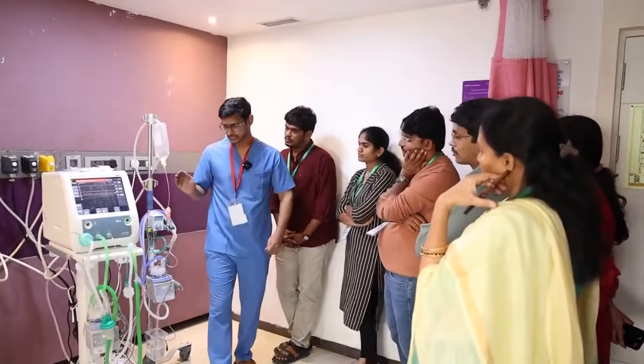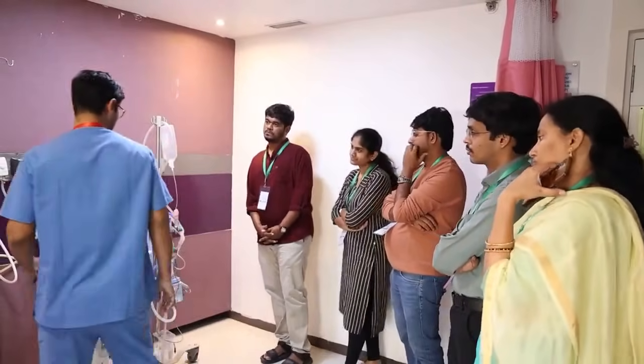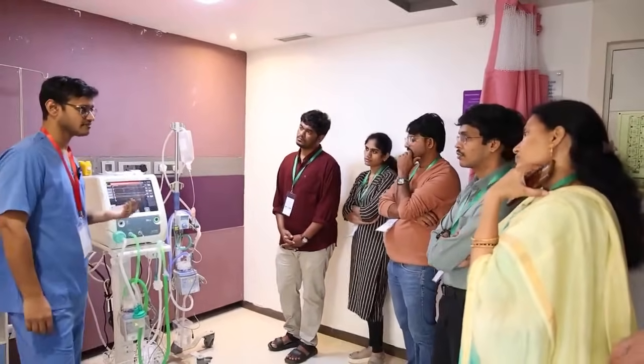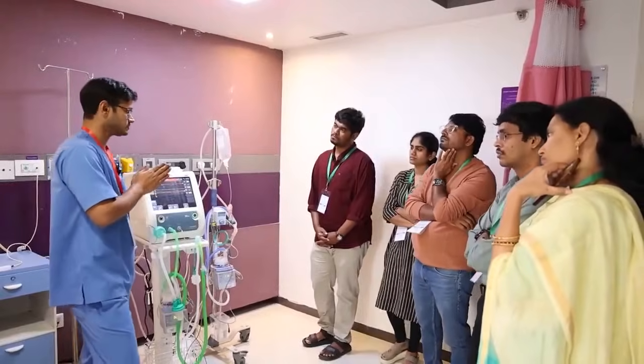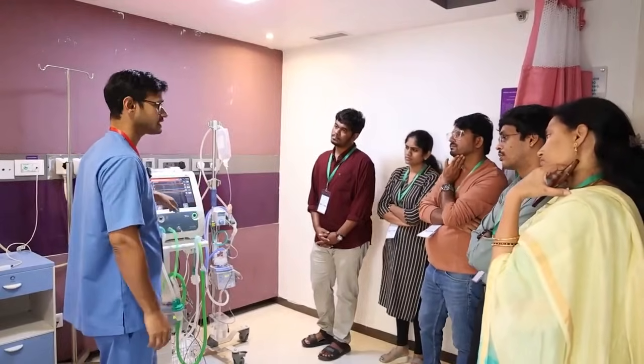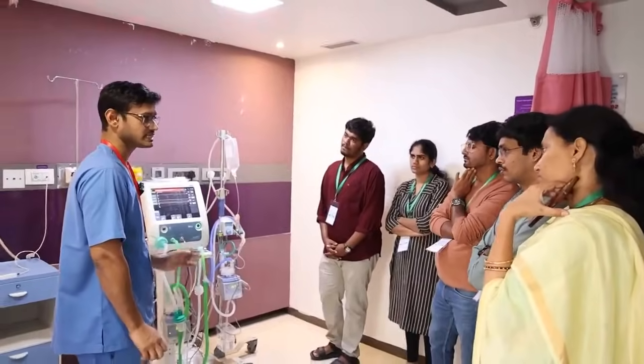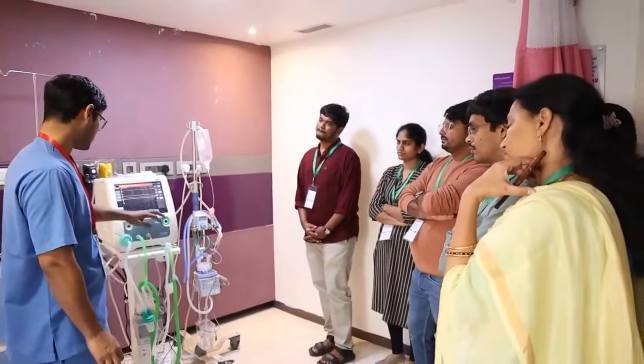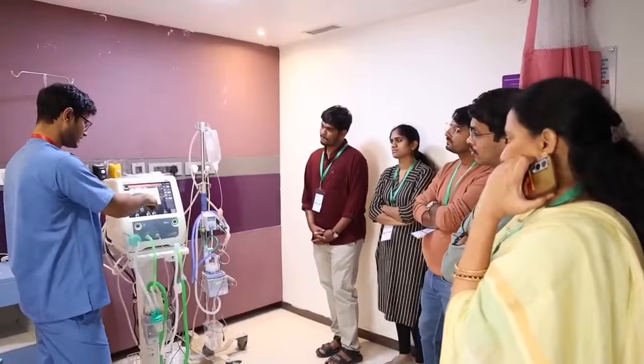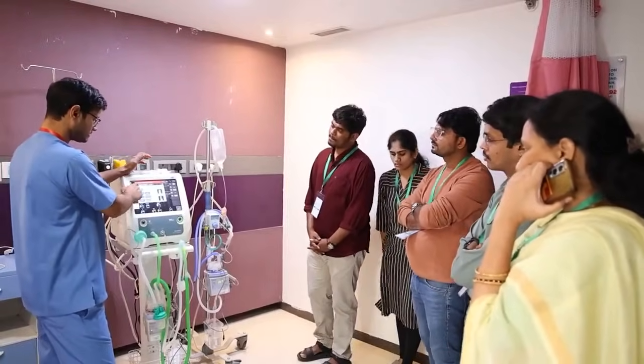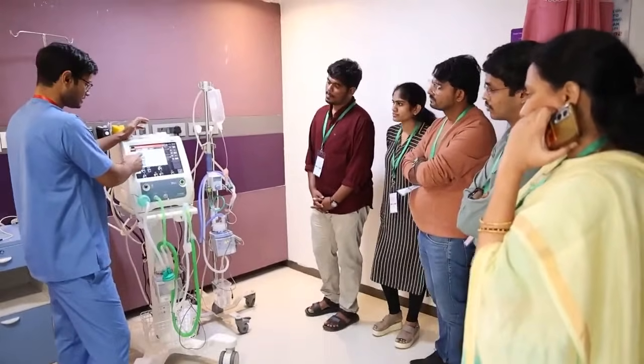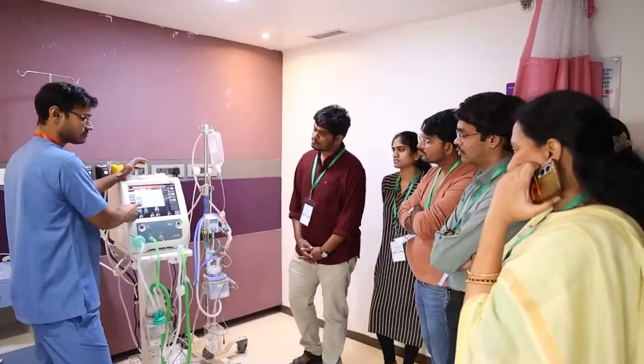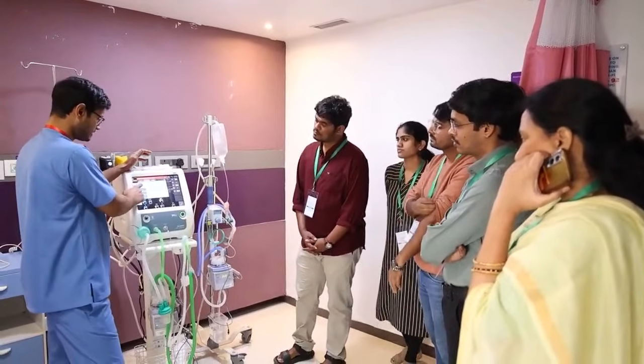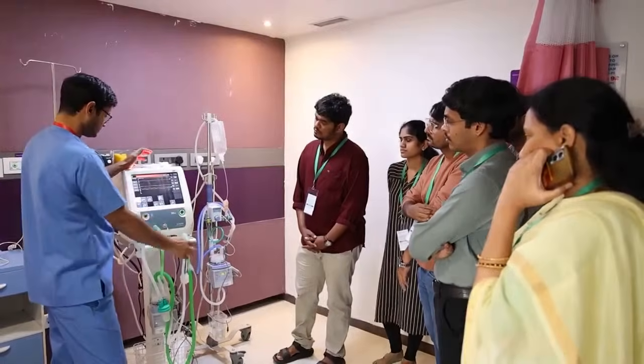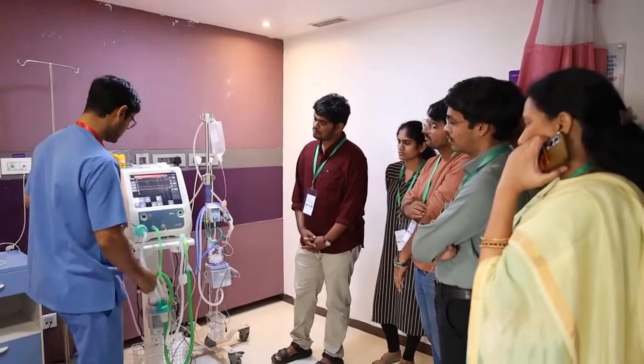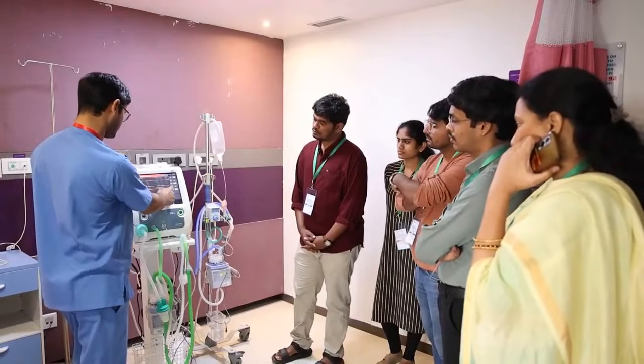Ventilator CPAP is slightly different from bubble CPAP, where in ventilator CPAP you have an expiratory valve which stops the flow of the expiratory gas, and then it generates the peak inspiratory pressure and positive end-expiratory pressure. Now when you come to a ventilator, you have a display like this. When you start, you have invasive mode and non-invasive mode, and in non-invasive you have NCPAP, NIPPV, and then nasal high frequency ventilation. If you press on this, now you can see we have kept a PEEP of 8.